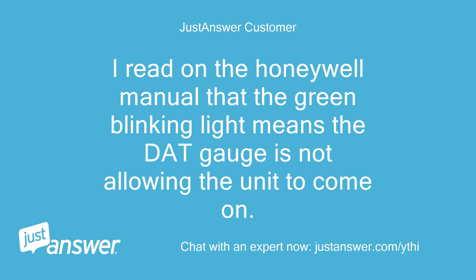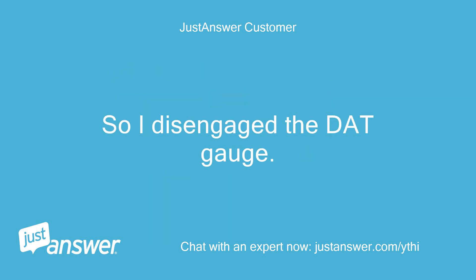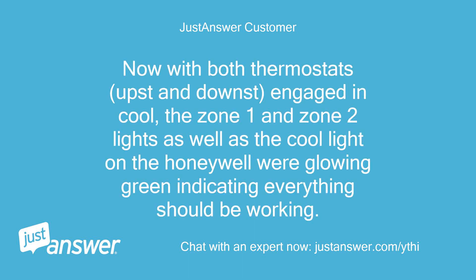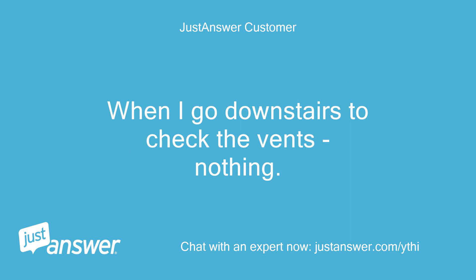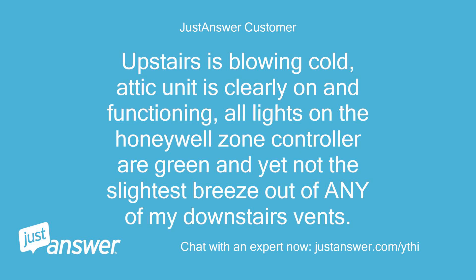I read in the Honeywell manual that the green blinking light means the DAT gauge is not allowing the unit to come on. So I disengaged the DAT gauge. Now with both thermostats — upstairs and downstairs — engaged in cool, the zone 1 and zone 2 lights as well as the cool light on the Honeywell are all glowing green, indicating everything should be working. The attic unit is clearly on and sounds like it is functioning fine. When I go downstairs to check the vents, nothing. Upstairs is blowing cold, the attic unit is clearly on and functioning, all lights on the Honeywell zone controller are green, and yet not the slightest breeze out of any of my downstairs vents. Thoughts?